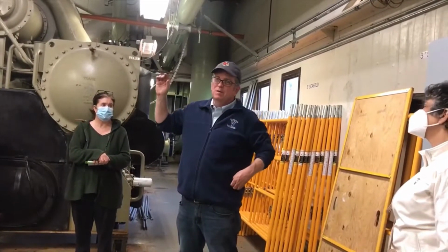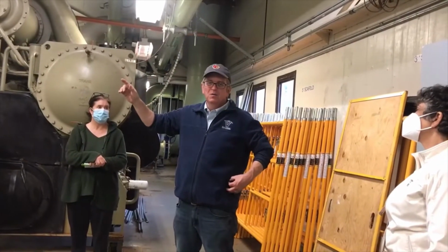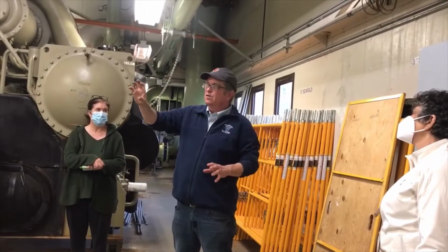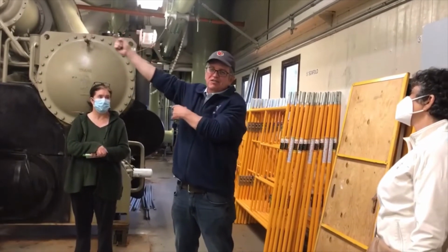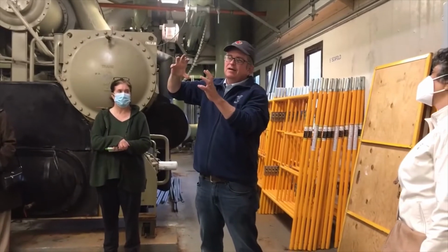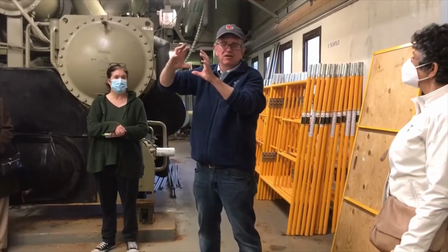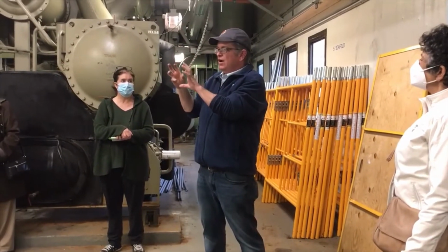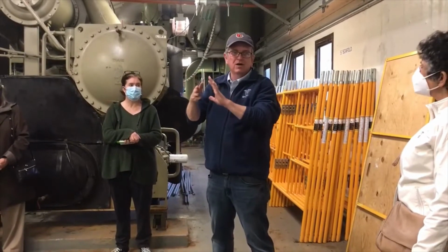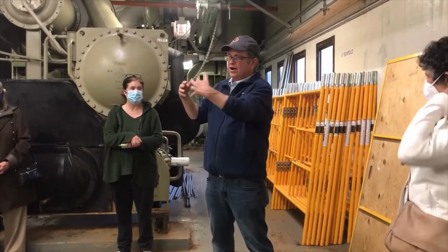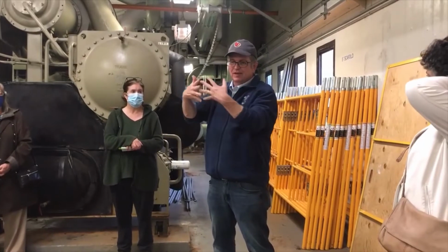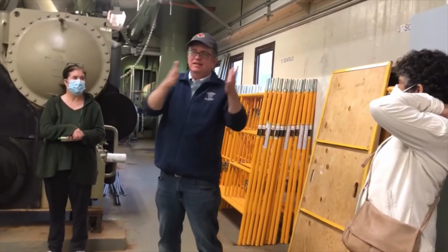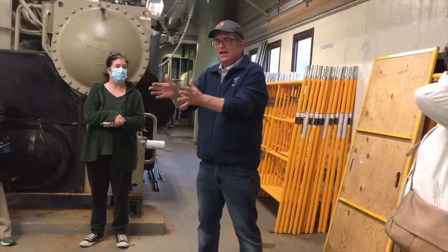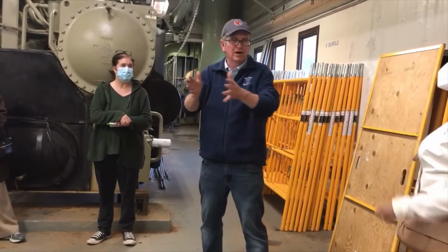But when we have the cogen running, before we do that, we run it through a heat exchanger that takes that 800 degree air and passes it across a coil, so that the water, again, they never mix, but it's a heat exchanger where they run across each other. And so you take the 800 degree air and you heat the 155 degree water.